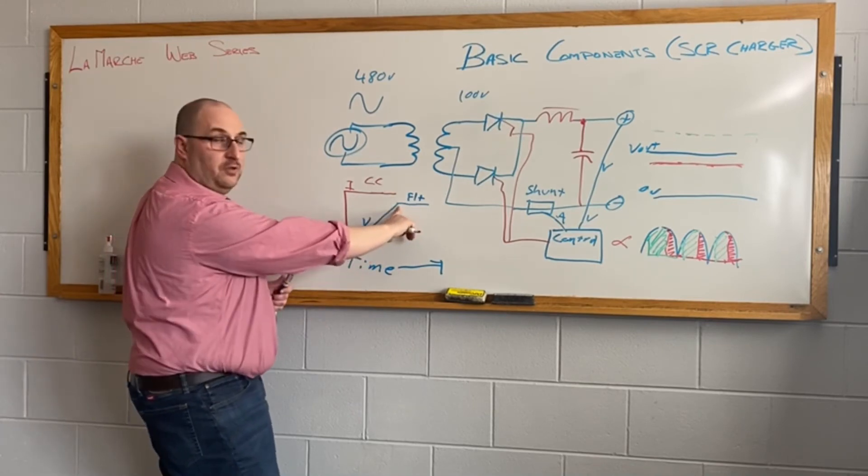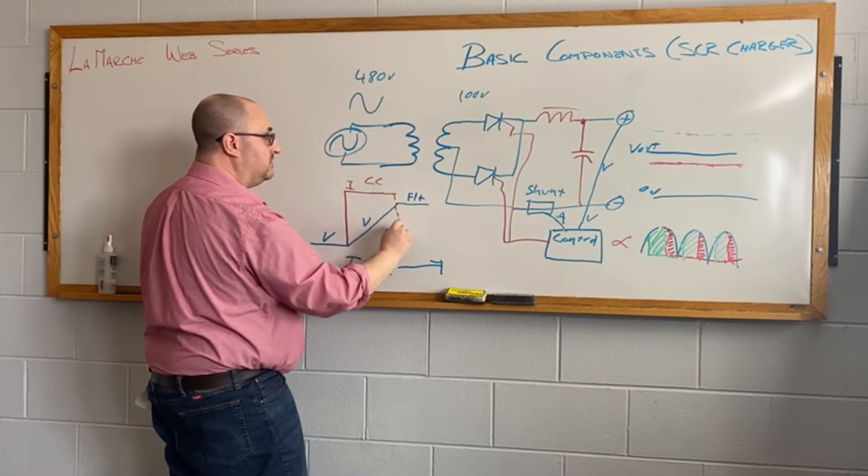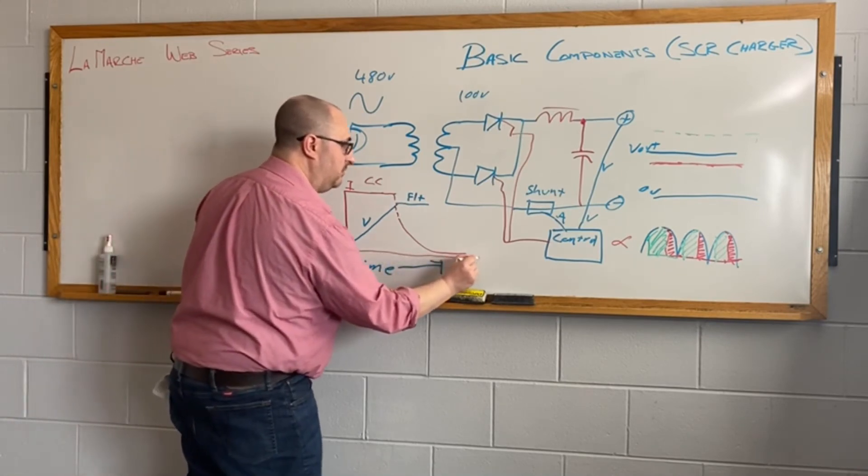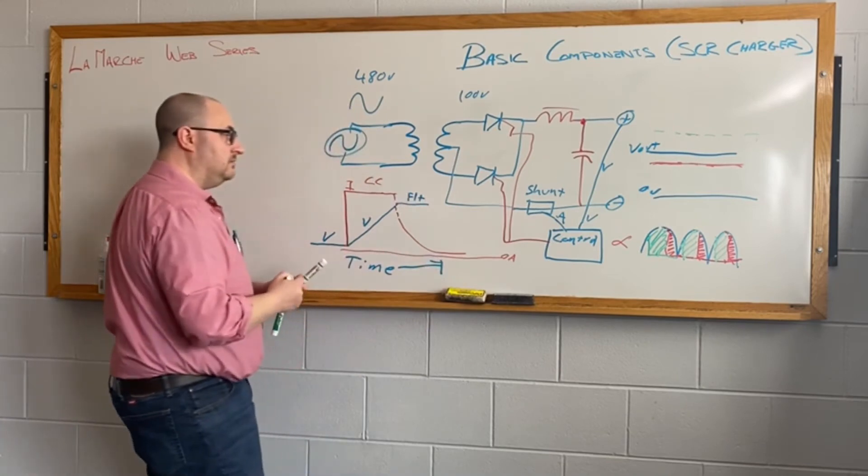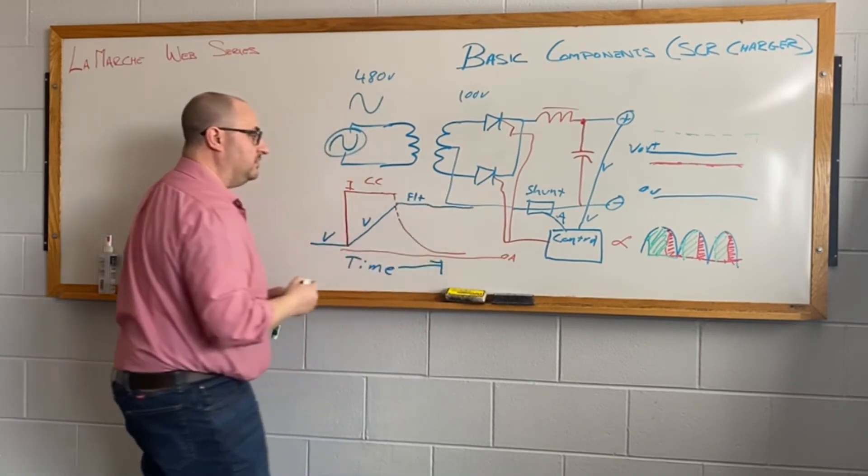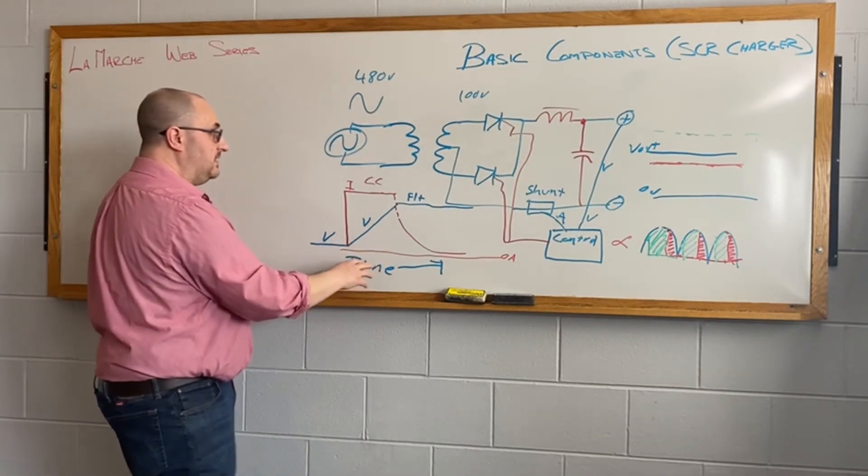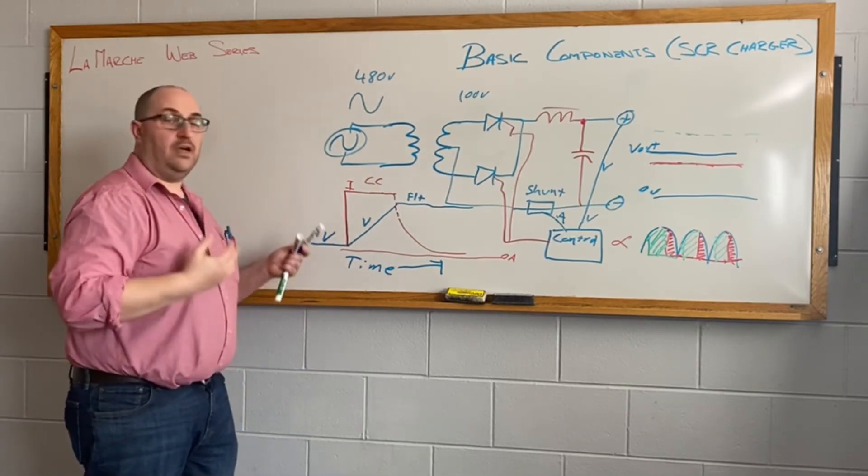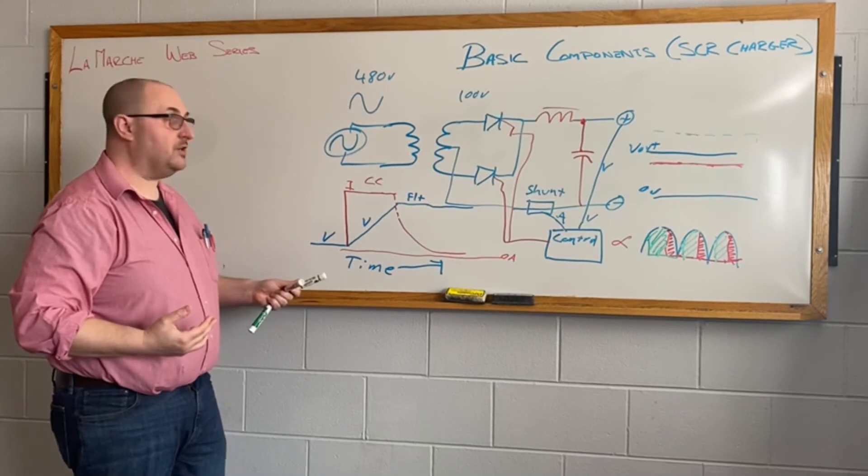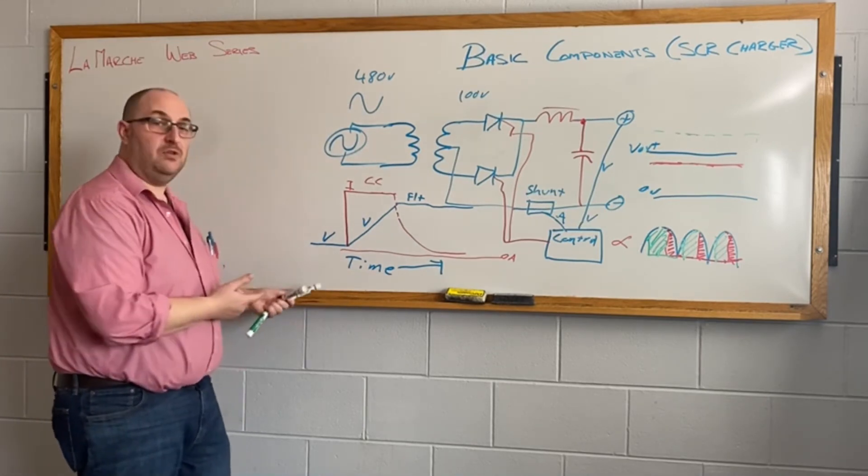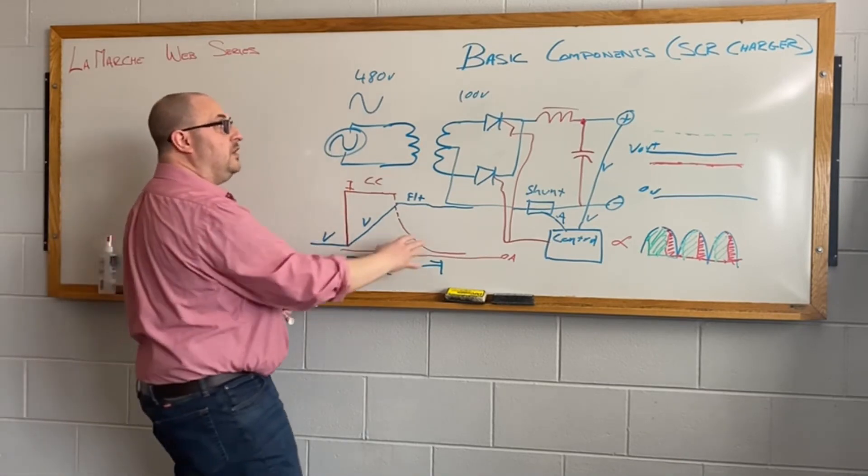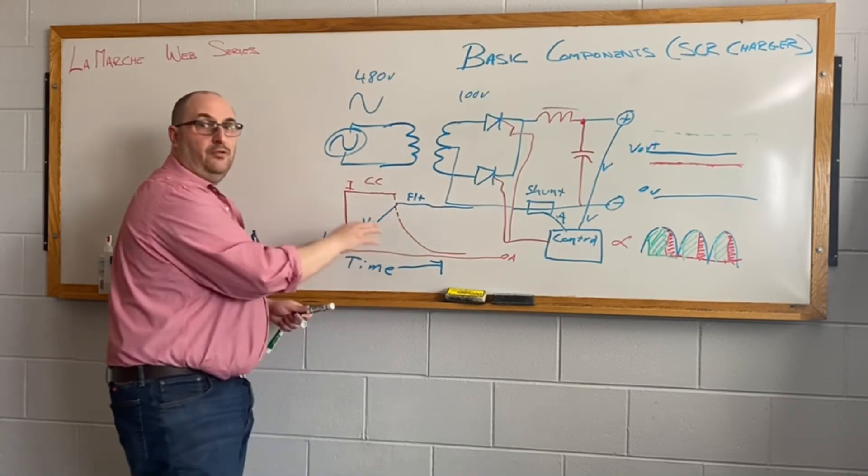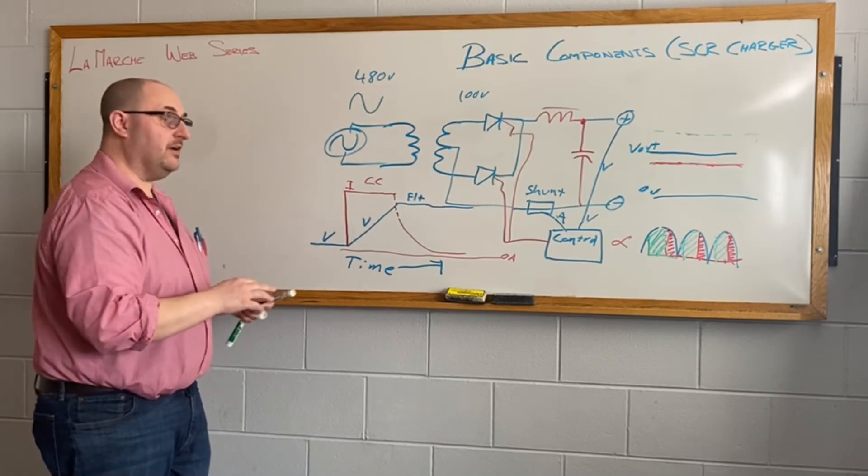Once it hits the float voltage set point, the current will start to taper down, and eventually it's going to hit an asymptote just a little bit above zero amps, where the float voltage will continue. So the idea of this is we need to be able to control this current because an empty battery will try to draw an infinite amount of current from the battery charger. That means it's not going to be healthy for the battery, and it's not going to be healthy for the charger either. So by controlling the recharge current and controlling the float voltage, we can now properly recharge just about any type of battery with this style charger.